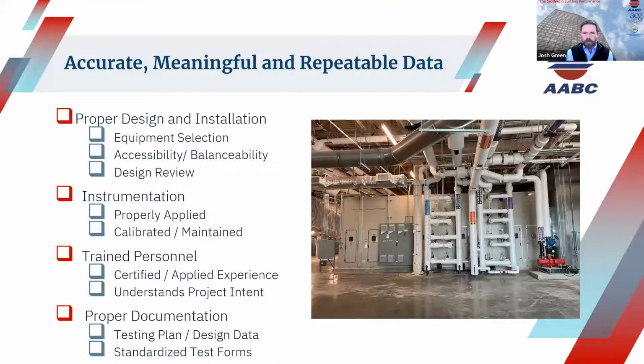One thing about data: I think it should be accurate, meaningful, and repeatable. There are some steps to ensure that we get that, and one of them is the design review of the plans, to verify the placement of the balancing devices, that they're going to be installed correctly, and that they're going to be accessible. The reviews can also provide recommendations for additional ductwork to minimize system effect losses and to allow us to get total airflow measurements by traverses. Using the proper instrumentation, including duct traverses, we make sure our instrumentation is calibrated, maintained, and applied properly.